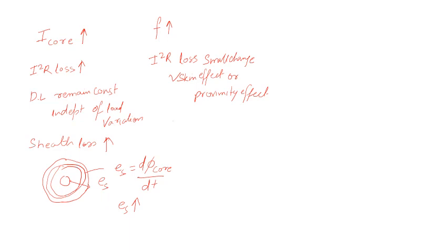What about the dielectric loss? Dielectric loss increases, because I have already told you that dielectric loss is directly proportional to your frequency. And what happens to your sheath loss? Sheath loss also increases because the rate of change of flux increases, so the EMF increases. So sheath loss changes with respect to frequency. Sheath loss also increases.